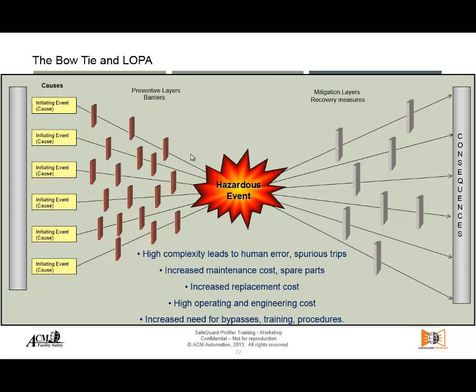Sometimes when you come from hazard and operability studies, you get too many safeguards — high complexity of scenarios because you have too many safeguards in there. When you have too many things that you don't really understand, that leads you to make unwanted errors. Nobody wants to make errors, but they happen, and when things are complex, we are prone to make more errors. Those errors will end up in false trips.